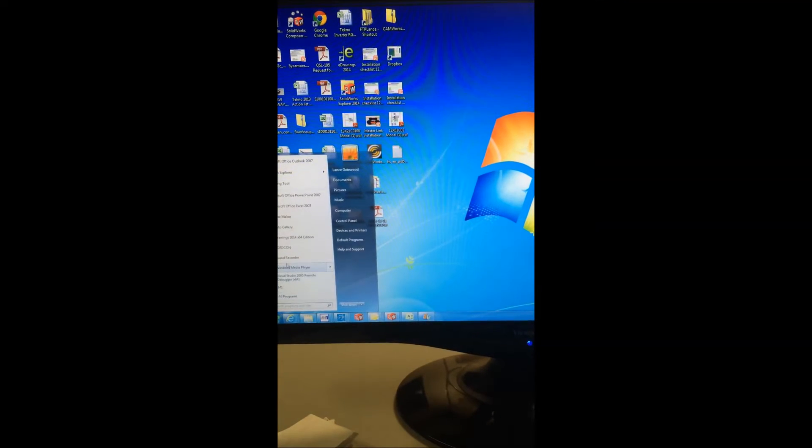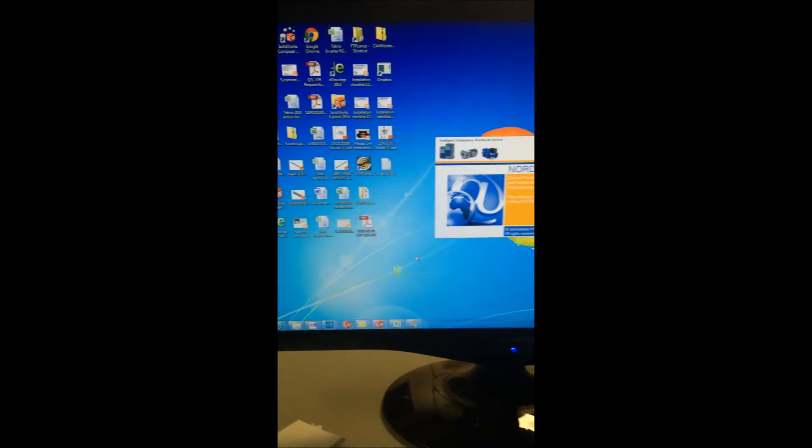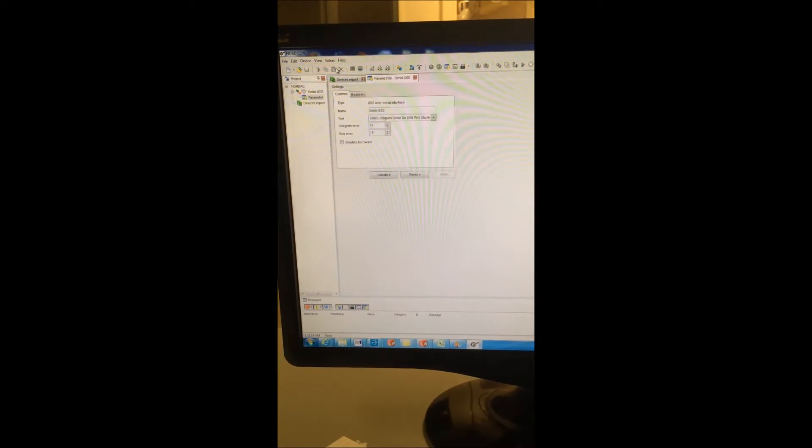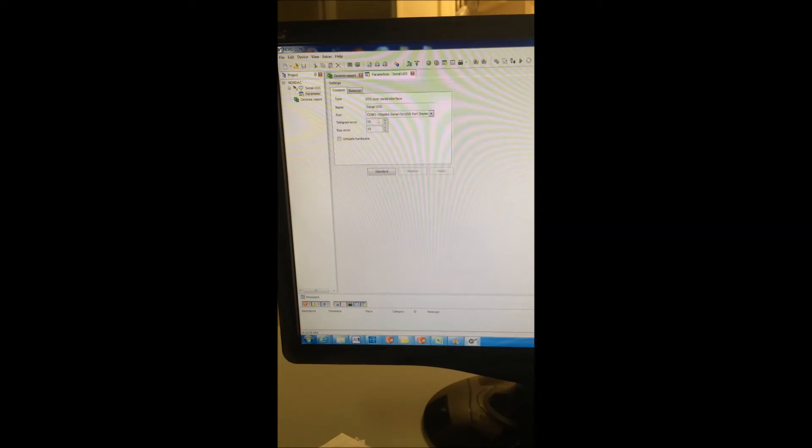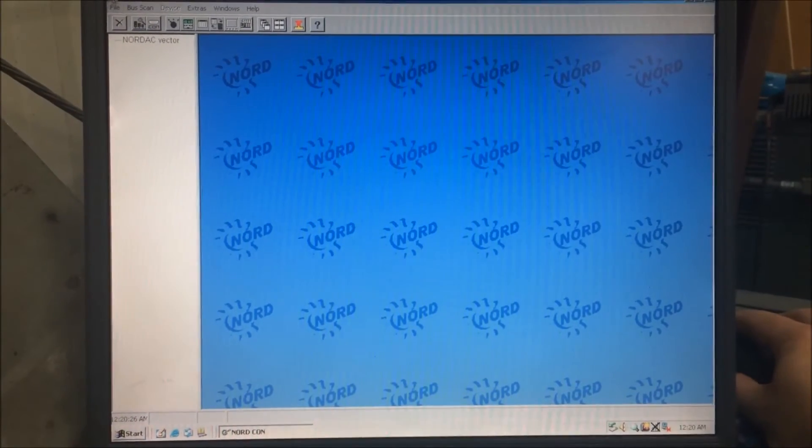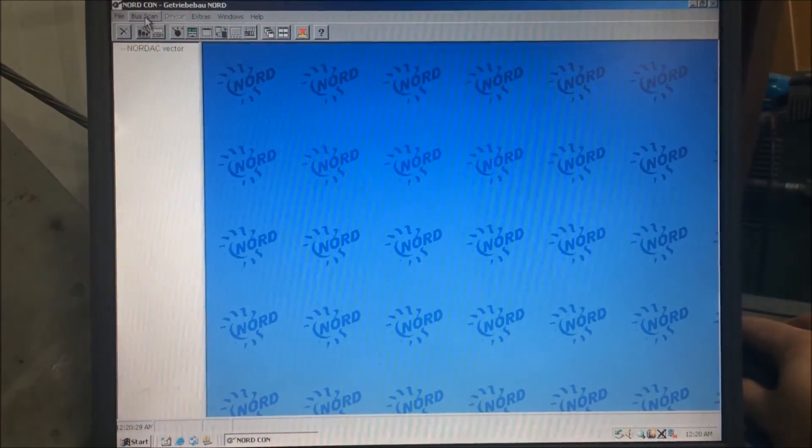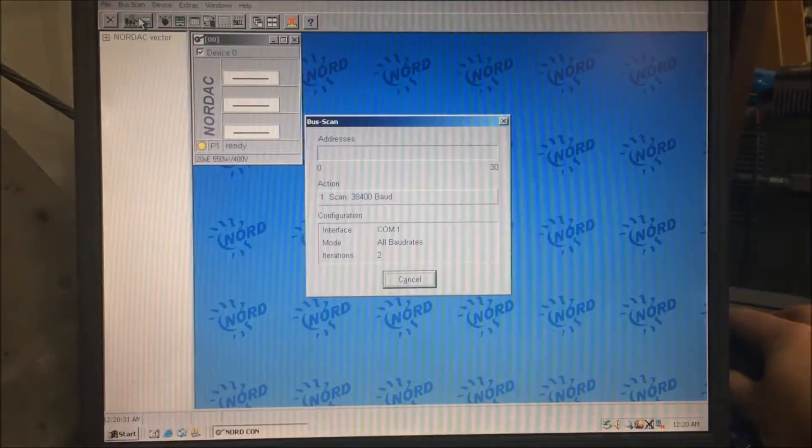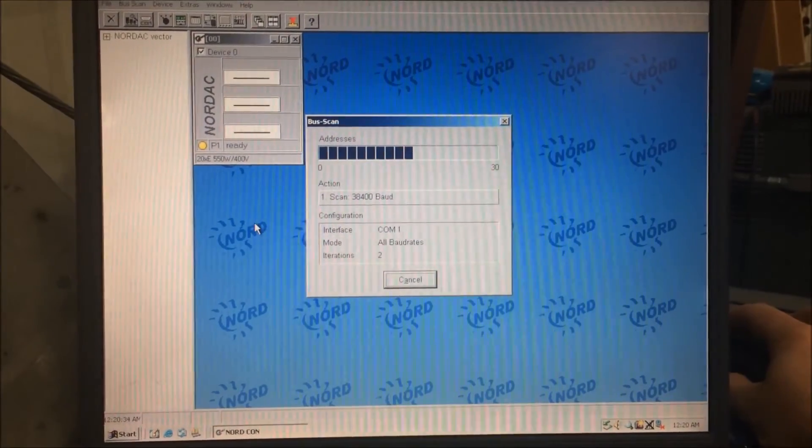Start the NordCon software. Go to the extras menu and select communication settings. In the dialog box below, select the correct communication port that you found earlier. Next, perform a bus scan from the menu above. The bus scan will find the appropriate motor that you're connected to.